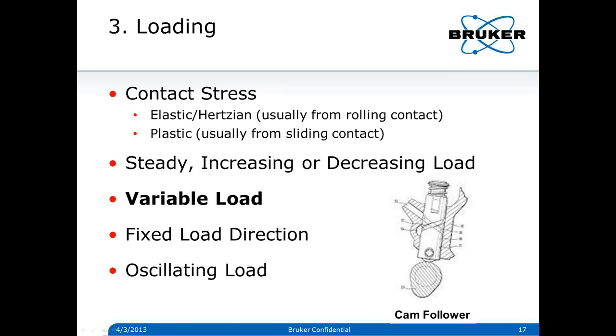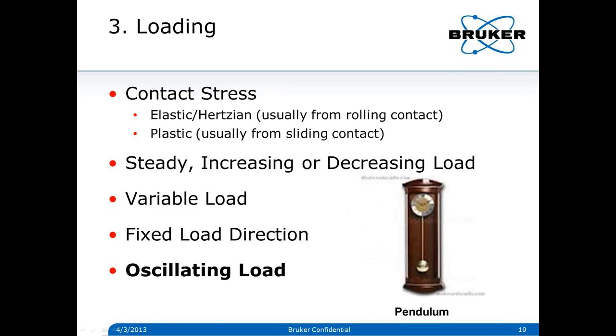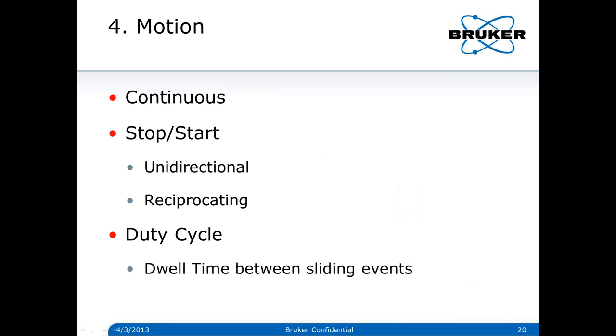You can have variable loading such as in a cam follower where changing the height changes the spring load. You can have a fixed direction load such as a rolling element bearing where the force is always in the same direction. Or you can have an oscillating load such as a pendulum where the point of contact changes. Changes in loading can also come from changes in speed or temperature which cause changing clearances — something we often forget when we do room temperature tests but real life involves higher temperatures.